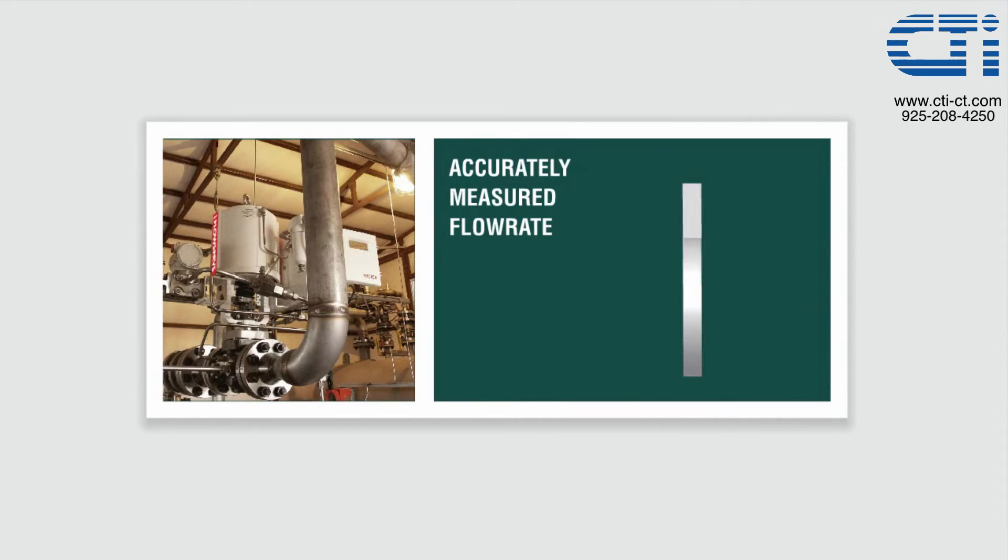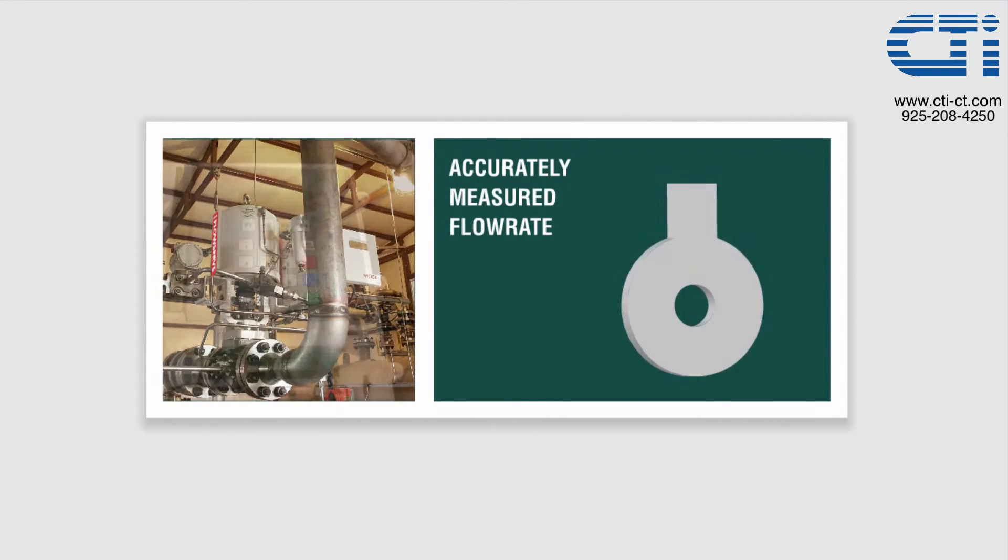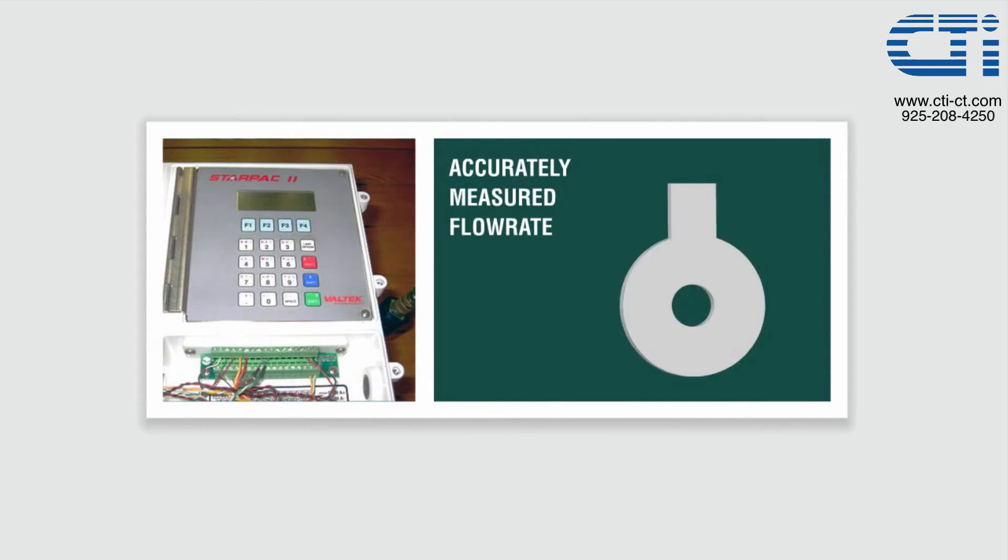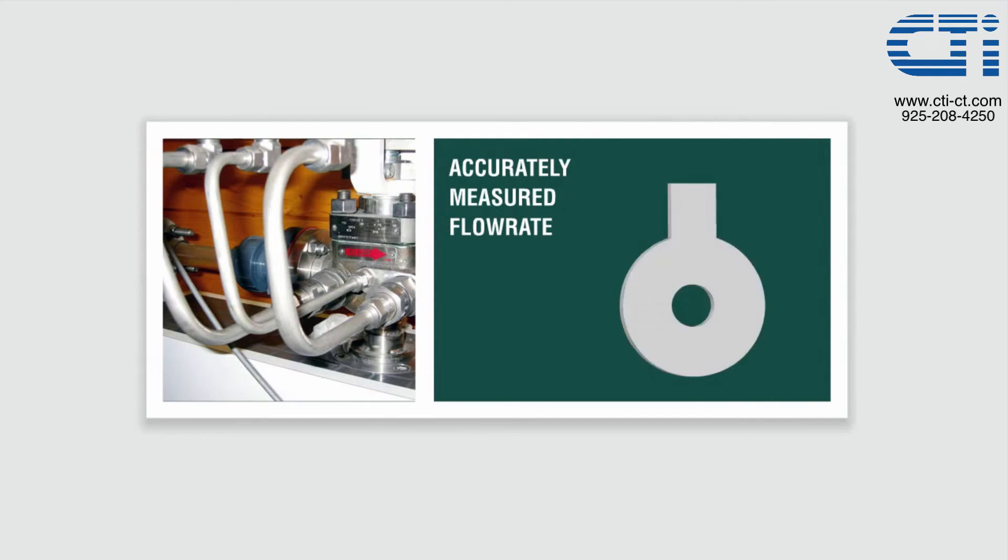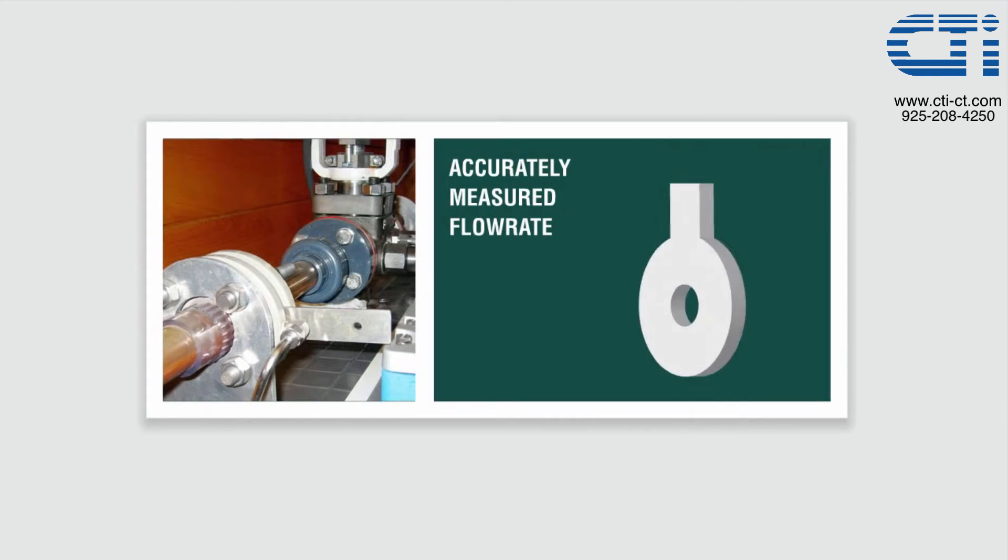The StarPac is a lot like an orifice plate, but with 10 to 50 times the measurable flow range and without the worry of leading edge wear and pipe insertion problems. The StarPac continues to accurately measure flow rate even if the trim wears because StarPac measures the overall flow capacity of the valve, which is unaffected by normal trim wear.